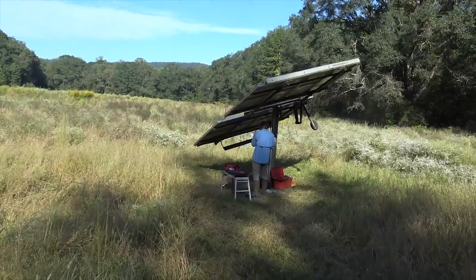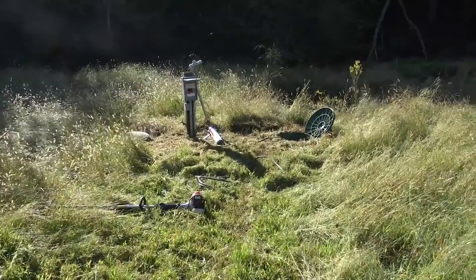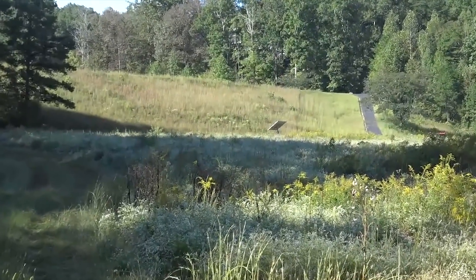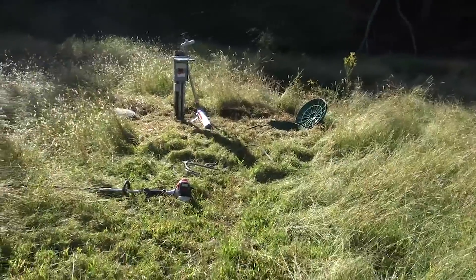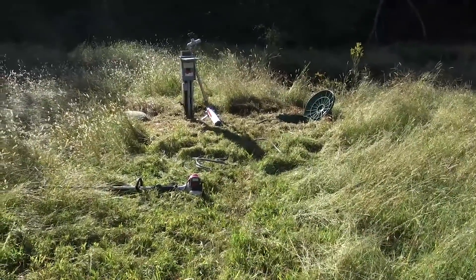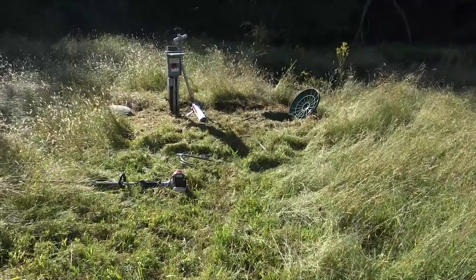Since the PV is already run under here to that tank, we're just going to splice in and bring the PV to the controller. This is our first attempt at a Franklin Fhoton — I've been seeing them at SPI and Intersolar, and the Franklin salesman came and visited and said to try it. We do a lot of Grundfos pumps, so it's nice to change it up. For this dirty water application, I think this is a better choice — rotor pumps don't do well here.